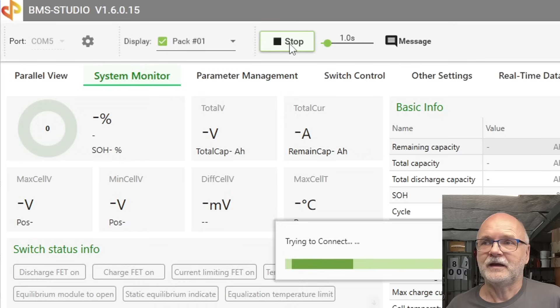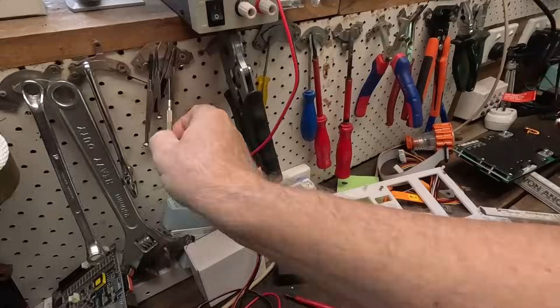I set the software into standalone mode, because we are connecting only one BMS at a time. I need to change this one to COM5, which is my virtual COM port for the RS485 adapter, and then I click on Start. Potentially nothing will happen, because the BMS is still asleep, so take a little screwdriver and wake it up.